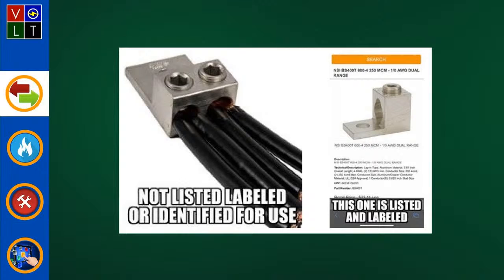Typically I do a lot of fire alarm work, and in fire alarm we use two conductors per terminal almost daily, and there's really nothing wrong with it. A lot of guys will say that when you come into your fire alarm nodes you should have one conductor per terminal. But then you get into some fire alarm panels where you have class 1 wiring coming into one compartment and you have to exit that compartment to go somewhere else, and you have limited space to do that.